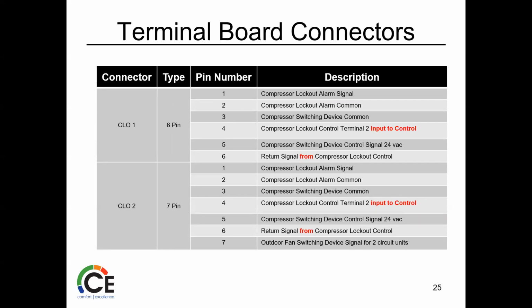The compressor lockout board that they label CLO. This seems to really perplex folks. It's actually just very simple. It's really just a relay board. So when we get that Y1 signal back from the economizer, the first thing it hits is terminal 4. So it comes right from the economizer. It goes through the board. There's a couple jumpers. As long as they're intact, it goes right to terminal 4. Then it jumps to 5 when there's a little jumper wire on the board.